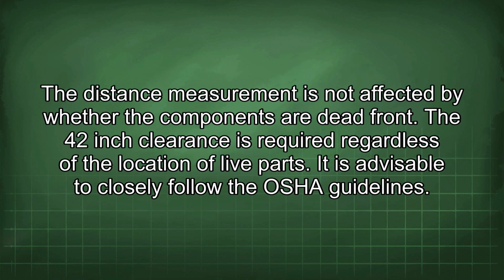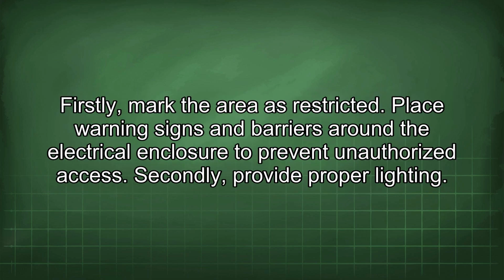The distance measurement is not affected by whether the components are dead front. The 42-inch clearance is required regardless of the location of live parts. It is advisable to closely follow the OSHA guidelines. Firstly, mark the area as restricted. Place warning signs and barriers around the electrical enclosure to prevent unauthorized access.